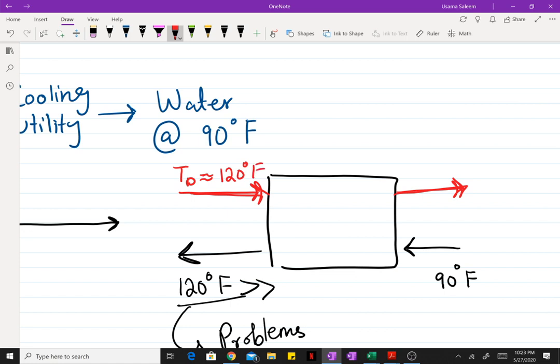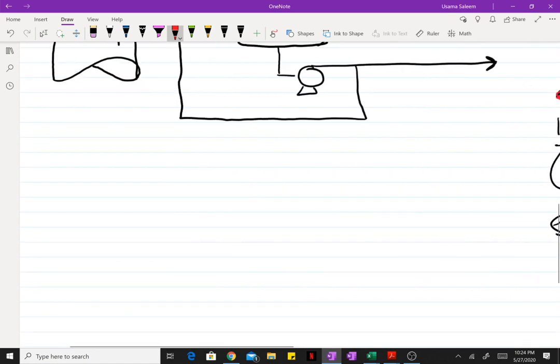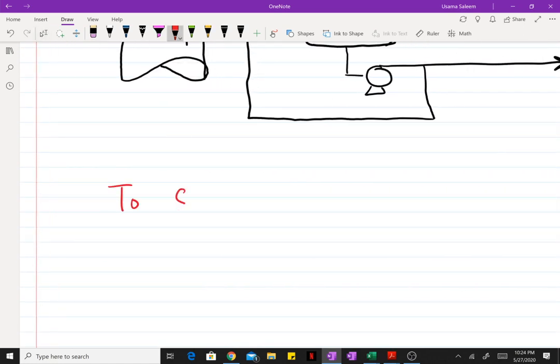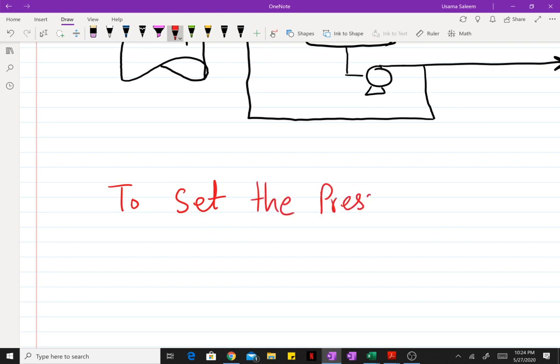If the distillate is entering at a bubble temperature of 120°F, then the exit temperature of the cooling water cannot exceed 120°F, so cooling water can safely be used. Also, if the temperature of the distillate is below the temperature of the cooling water, there is no point in using cooling water as a utility since you won't be able to cool something with water that's at a higher temperature.